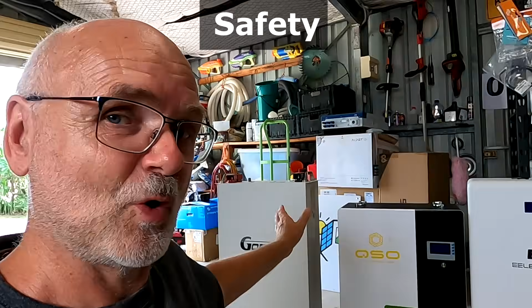Gobel Power is the only manufacturer here which actually supplies the case with a circuit breaker. All the other batteries have either a fuse inside or, like the QSO battery, nothing. The QSO battery has neither a fuse nor a circuit breaker, no protection at all, just the BMS, nothing else. So from a pure safety perspective, Gobel Power gets another point for providing a mechanical circuit breaker.